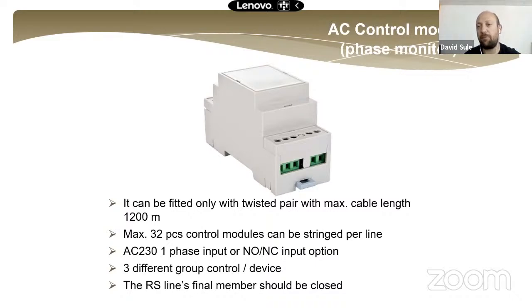Connecting into one panel is enough, because if we use a network, one panel can send this information to other panels. This AC230 device is monitoring one phase input or a normally closed or normally open signal. One of these modules can control three different light groups. For example, if this module is installed on the second floor and the second floor sub-dB has a power failure, this device will turn on the second floor emergency light, the staircase light, and the ground floor light. These three groups are perfect to show the exit way from the building.